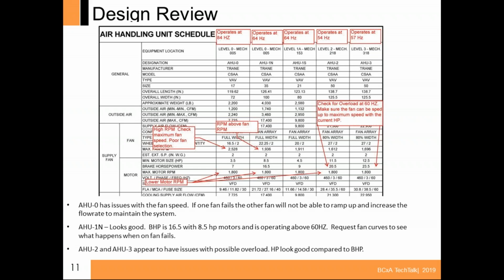Now they're bringing a nominal horsepower motor, nominal speed motor of 1,800 RPM. So I looked at that, I said, you know, that motor is running at 84 hertz. Both of them are running 84 hertz to maintain that pressure and flow. And so I don't think the owner knows what they're looking at a lot of times.